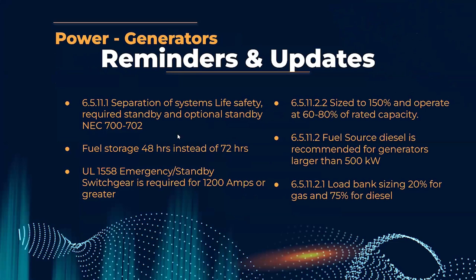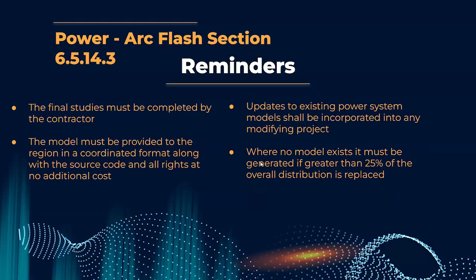Generators, the first 4 bullets here are reminders. The last 2 were changed quite a bit. In previous versions of P100, we limited gas generators at 350 kW, and we now say we recommend diesel for 500 kW and larger. We also changed our load bank percentages based on NFPA 110 testing requirements: 20% for gas, so that there's some load there, and 75% for diesel for the testing requirements.